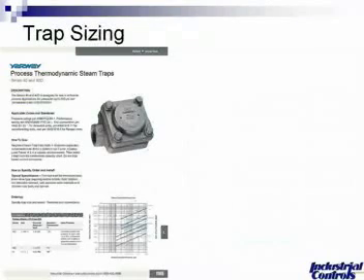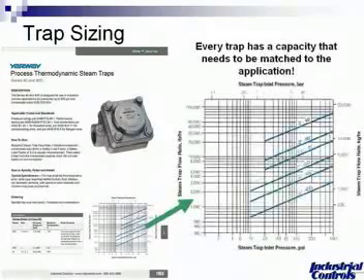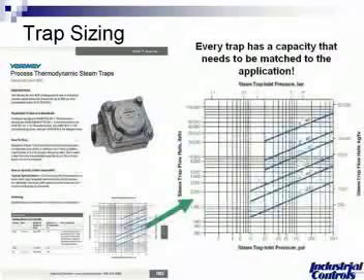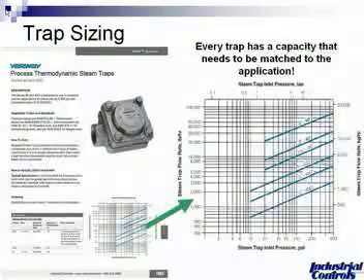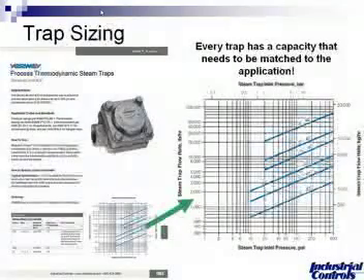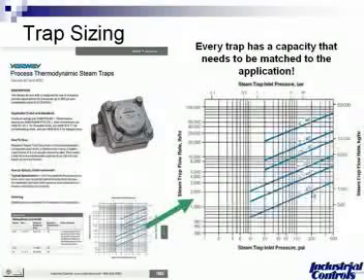This is another page out of our catalog showing a process thermodynamic steam trap produced by Yarway. We show you how to size and select — every trap has a capacity that needs to be matched to its application. As an example, if you look where the arrow is pointing on the left-hand side, a steam trap flow rate of 2,000 pounds per hour — moving across to an inlet steam pressure of 200 psi, the intersecting selection would be a half-inch 40D model steam trap produced by Yarway. This is on every page in our catalog, and we can also assist you with sizing and selection if you contact Industrial Controls.